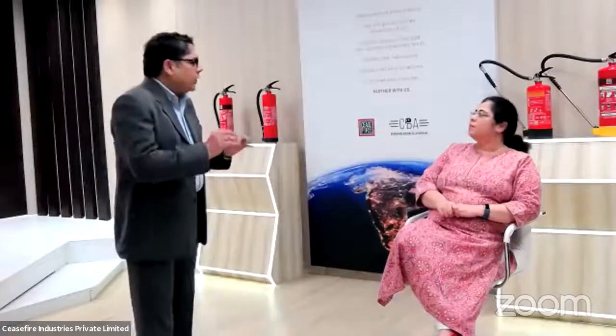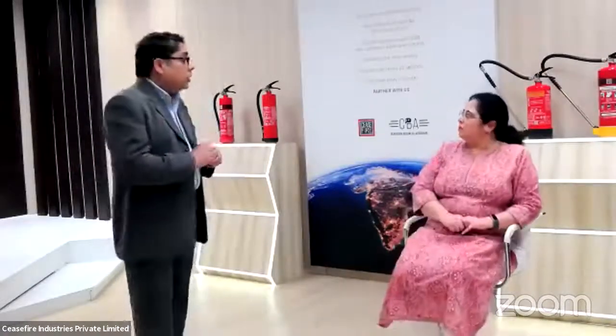These small extinguishers work on quartzoid technology, with a small bulb that can sense fire within small enclosures and operate to extinguish it using a minimal amount of agent, ranging from about 100 grams to 500 grams. We have the quartzoid bulb in various temperature ranges too, 57, 68, and 93 degrees centigrade. Depending on your ambient temperature, you can select the appropriate extinguisher for your panel.